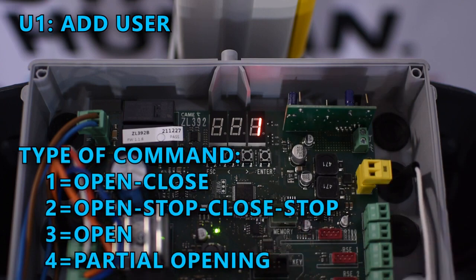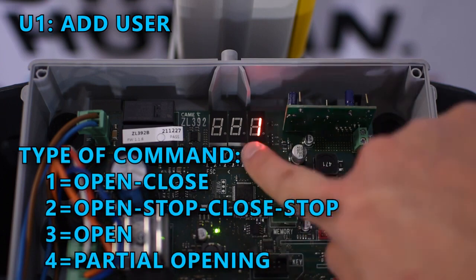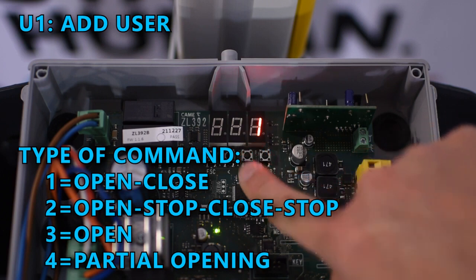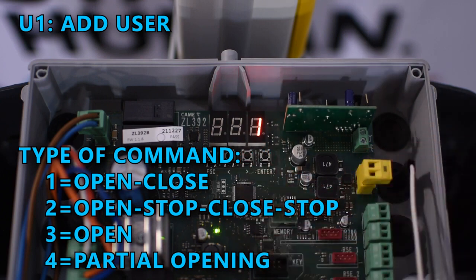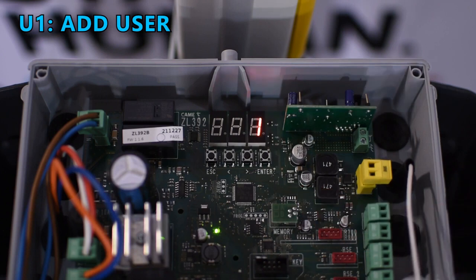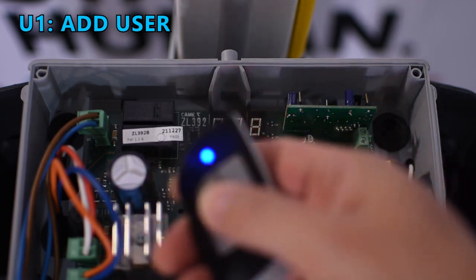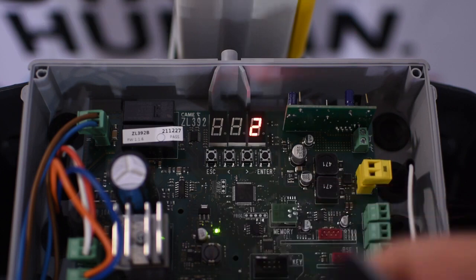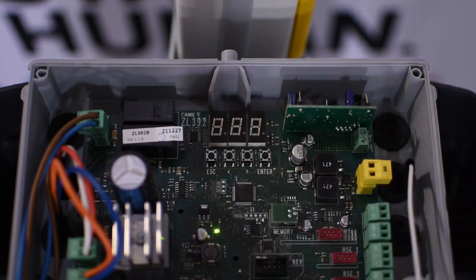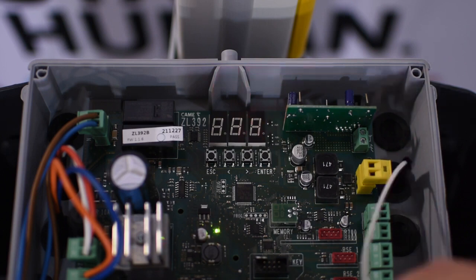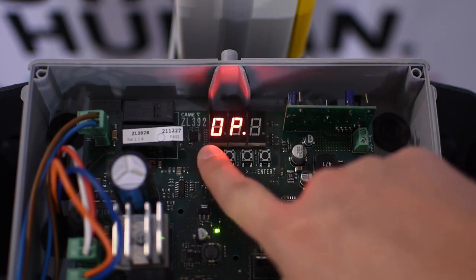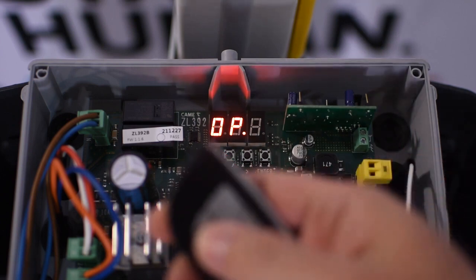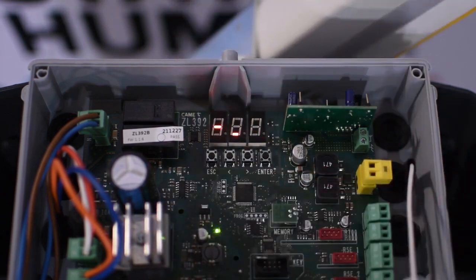Press Enter and it will show the number 1 indicating the command you want to assign to the button of the remote control. Select which type of command you want and press Enter. Then a number is going to blink indicating that it's ready to receive the signal from the remote control, so press the button you wish to program. That signal is going to be stored in the user number that was blinking before. Now it's blinking the number 2 because it's ready to receive another signal and it's going to be stored in the user number 2. On this board we can store up to 250 users.